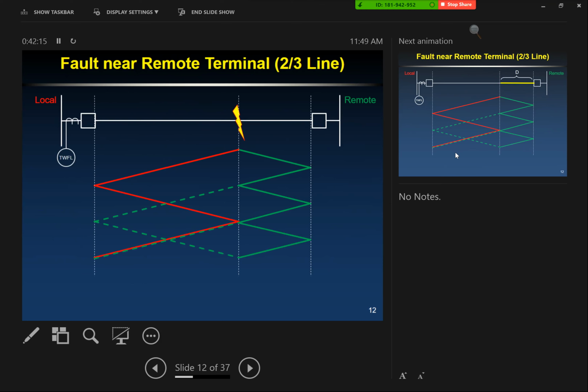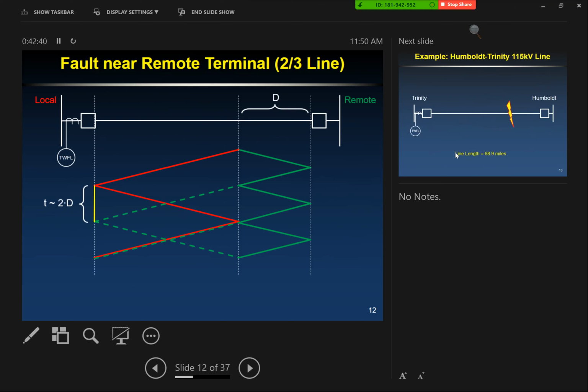So now, again, our traveling wave fault location relay has recorded its first waveform to arrive, second waveform to arrive. This second waveform to arrive now was the bounce off of the remote end, right? So now we are interested in this distance between the remote end and the fault. We can see visually that aligns with that point on the Bewley lattice, and follow it back to where the relay is recording.